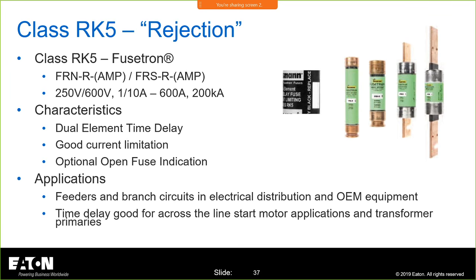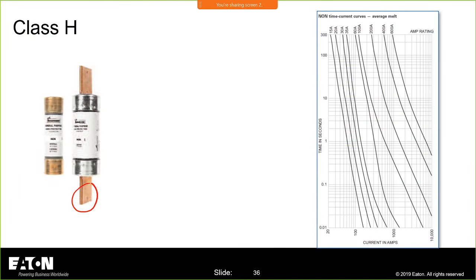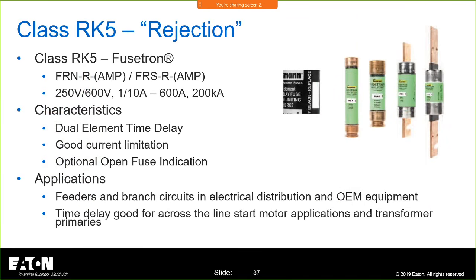These are the real workhorses of the fuses. These are your class RK5 rejection. R is for rejection, because they've got the rejection features on them. You know, they've got these little nubs on the end so that you don't put the wrong fuses in. You can't put a class H in place of this fuse because it needs to have the slot. The class H does not have a slot on either end, and there's no rejection features on it. So you can't put that fuse into the holder that's designed for these, which gets to that one question. I'm not going to be worried about putting a lower interrupting rating or a lower capability fuse in this because we build in rejection features. Another nice ease of use perspective from a fuse.